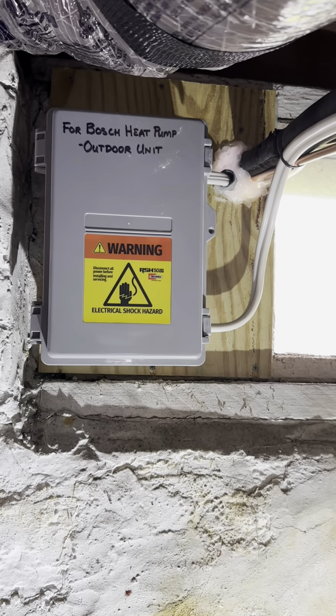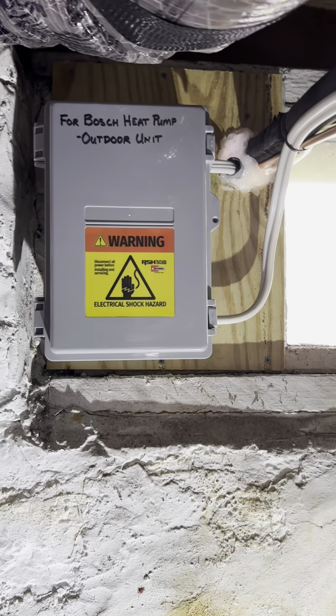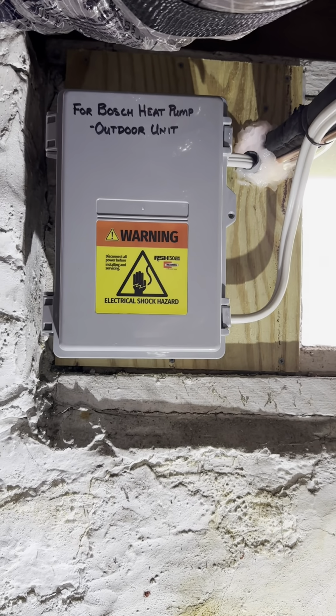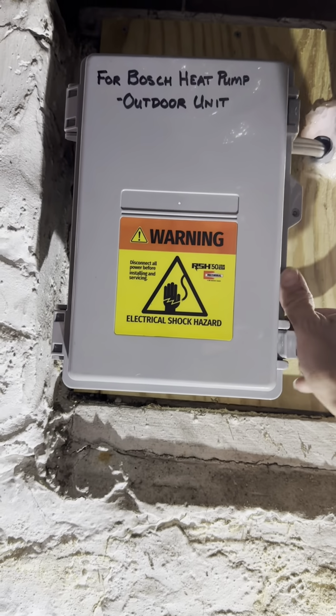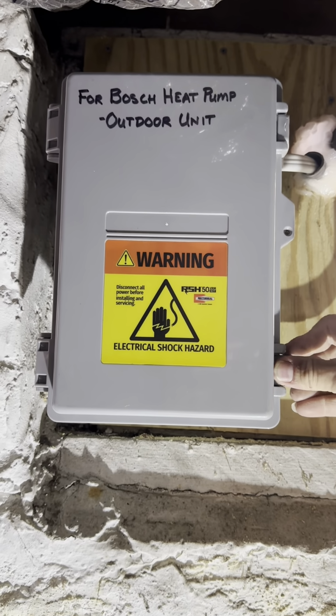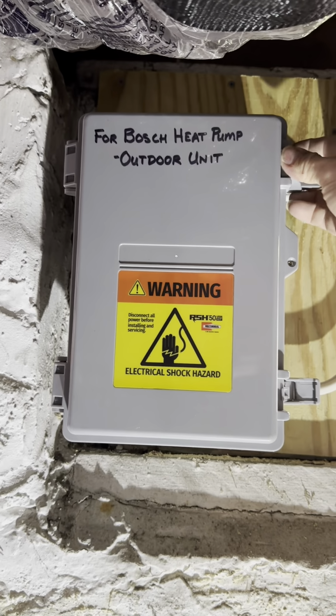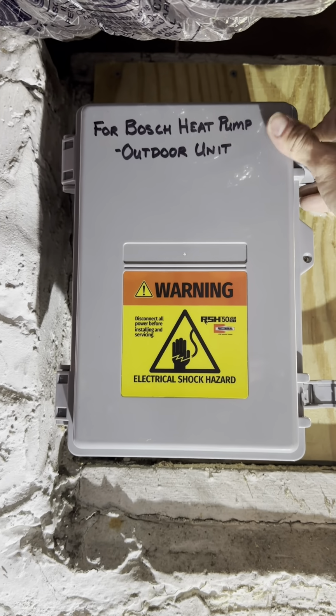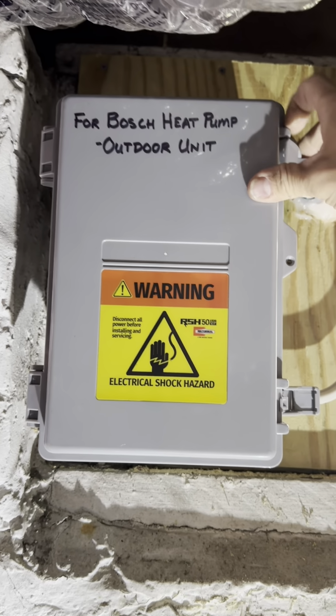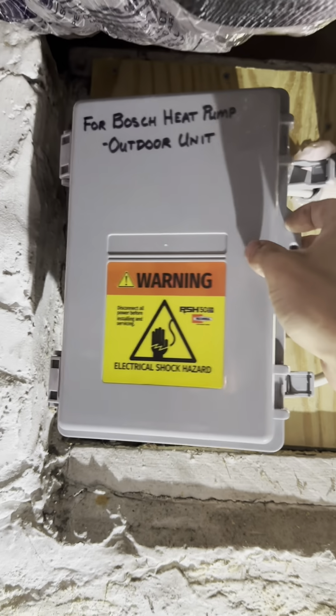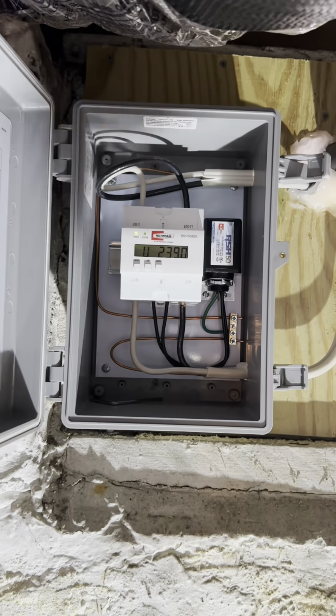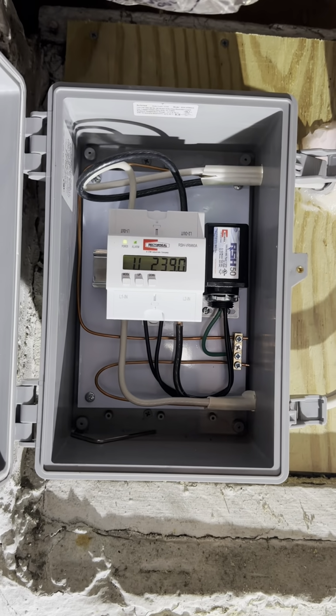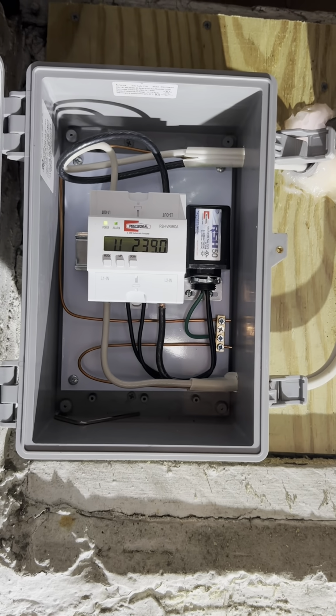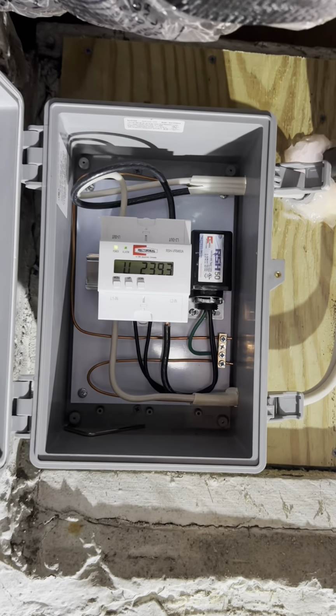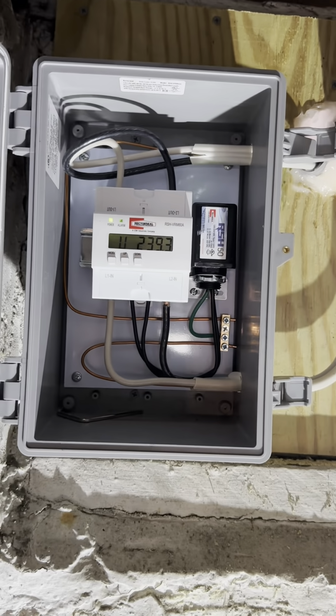So at Freedom Mechanical, for our Bosch heat pumps, we typically install a voltage monitor and surge protector on our newer systems. This is something we're starting to do to help protect the homeowner's investment. Once the warranty is gone, we want to make sure that that expensive control board is covered. So as you can see, we have 239 volts right now. I have some limits set on this, so this is something you'd want to pay attention to.